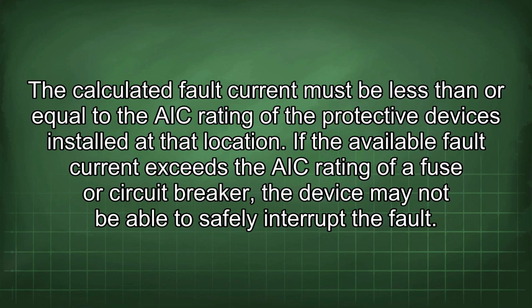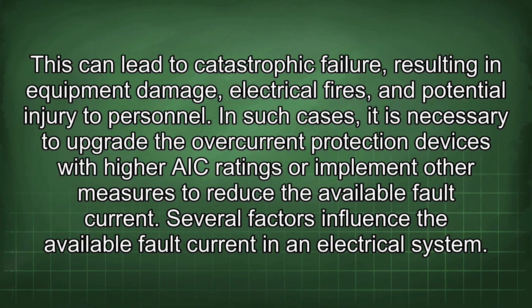If the available fault current exceeds the AIC rating of a fuse or circuit breaker, the device may not be able to safely interrupt the fault. This can lead to catastrophic failure, resulting in equipment damage, electrical fires, and potential injury to personnel. In such cases, it is necessary to upgrade the overcurrent protection devices with higher AIC ratings or implement other measures to reduce the available fault current.